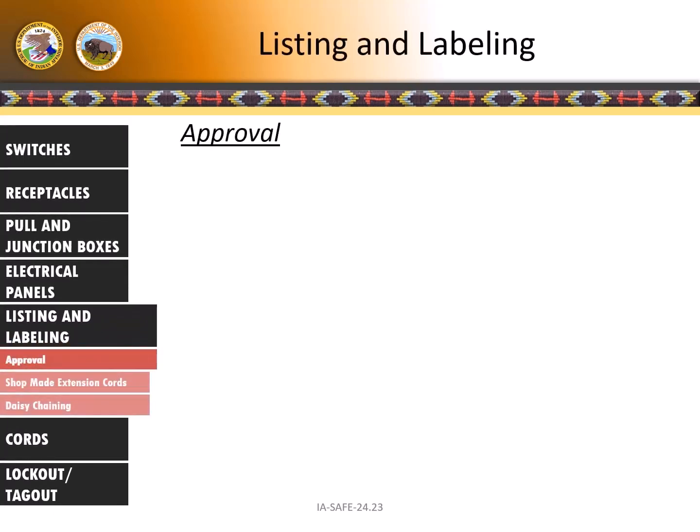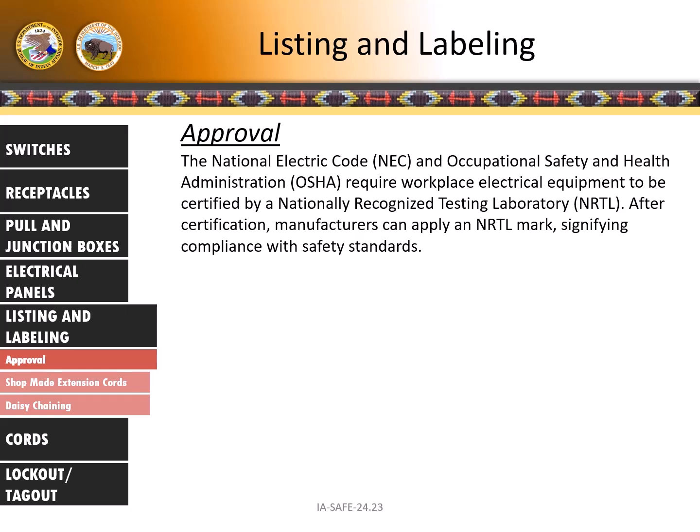Approval. The National Electric Code, NEC, and Occupational Safety and Health Administration, OSHA, require workplace electrical equipment to be certified by a nationally recognized testing laboratory, NRTL. After certification, manufacturers can apply an NRTL mark signifying compliance with safety standards.